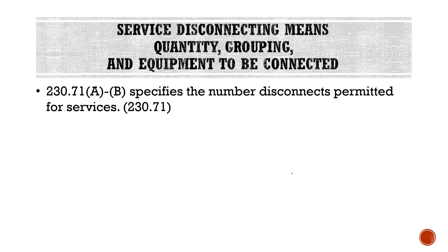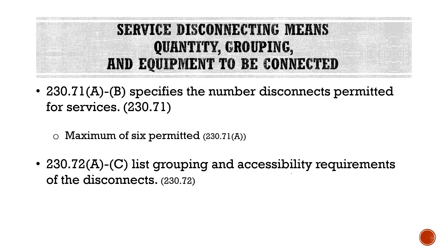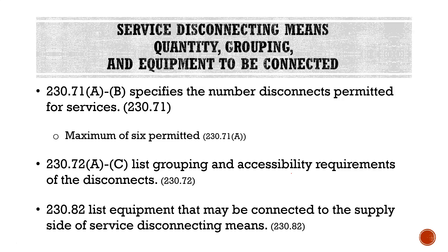Looking at our service disconnecting means, we have quantity, grouping, and equipment to be connected to the disconnect means. Section 230.71A through B specifies the number of disconnects permitted for services — a maximum of six is permitted for any service. We cannot exceed six disconnects for any given service. Section 230.72A through C lists the grouping and accessibility requirements of the disconnects, and Section 230.82A through C lists the equipment that may be connected to the supply side of the disconnecting means. Sections 230.72 and 230.82 cover general ideas about what we have to do and how the service disconnecting means can function.